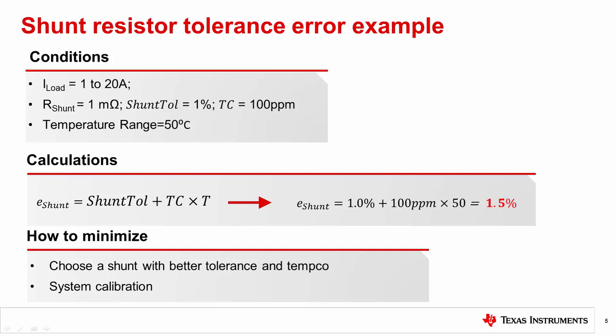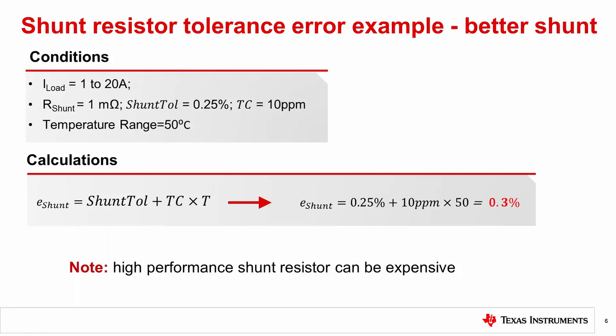How do we make it better and minimize this error? There are two possible ways to approach this. First, you can choose a high performance shunt, which means choosing a shunt with low initial tolerance and low temperature coefficient. Second, you may take advantage of system calibration. Let's take the same example from the previous slide, but substitute the shunt with one that is much more accurate. Here, the initial shunt tolerance is 0.25%, and the temperature coefficient is 10 ppm. As you can see, the resulting shunt error is only 0.3%.